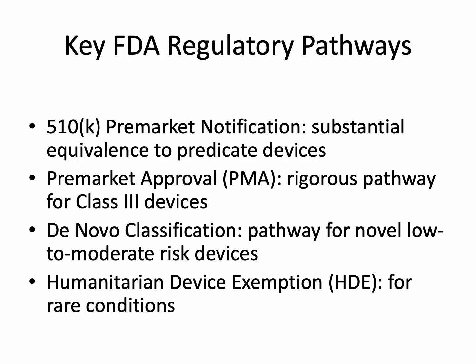The de novo pathway allows novel devices with low to moderate risk to establish a new device classification when no predicate exists, facilitating future 510(k) submissions for similar devices. Finally, the HDE pathway is intended for devices addressing rare diseases affecting fewer than 8,000 individuals per year in the U.S., focusing on safety and probable benefit rather than definitive effectiveness. Selecting the appropriate pathway early is critical for efficient development, study design, and resource allocation, ensuring that regulatory expectations are met and time to market is optimized.